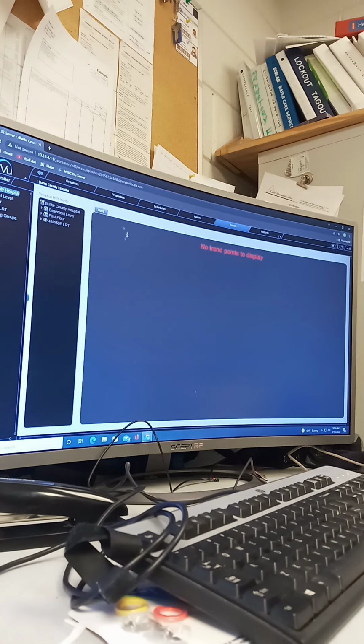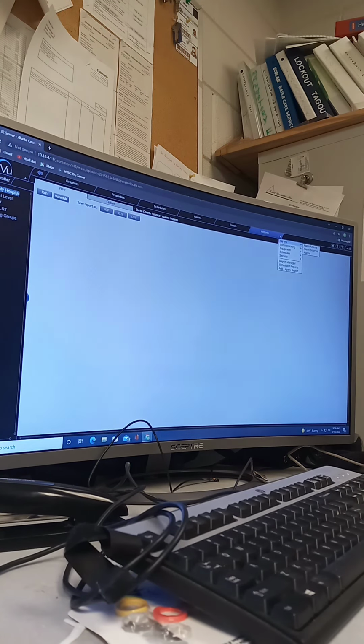Again, if something pops up and says accept or cancel and you're not sure what to do, just hit cancel. You're out. And the last one's reports. Right? So if I click on reports, these are all the types of reports. I can run an alarms report. We talked about that. Commissioning equipment, those are reports that somebody like Ryan or myself would run. We want to go in after we did a commissioning of a job and look at all the points of control, how we left them. And we do that for our own as-built needs for a job and stuff like that.